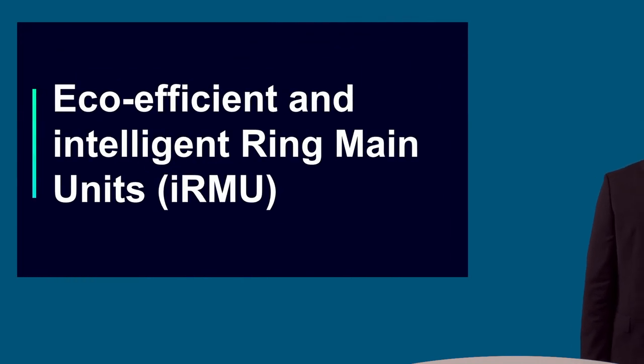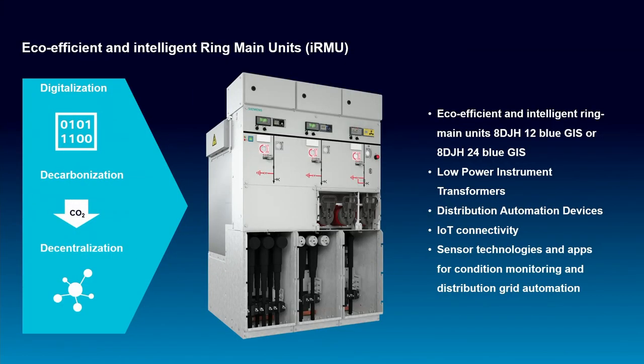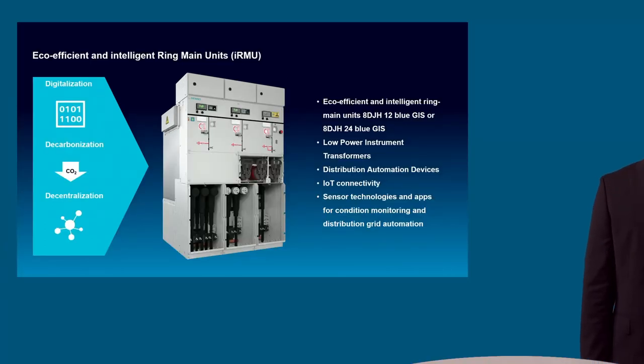Let's first have a look at the eco-efficient and intelligent ring main units from our 8DJH family. The three Ds — digitalization, decarbonization, and decentralization — have influenced the requirements on the design of gas-insulated ring main units, which have used SF6 as insulation gas for the last 35 to 40 years. Decarbonization has pushed us to develop an alternative concept to prevent the use of SF6. Digitalization has brought us to implement further IEDs and sensors in the RMUs. Decentralization is the driver for more and more distribution grid automation functions to master the challenges of e-car charging and renewable energy supplies on the distribution grids.